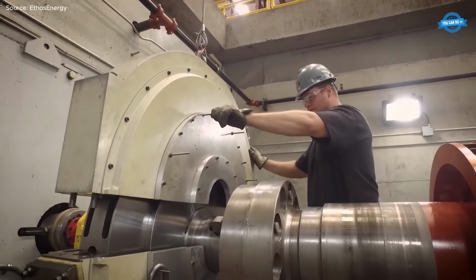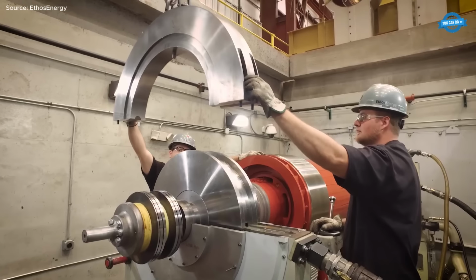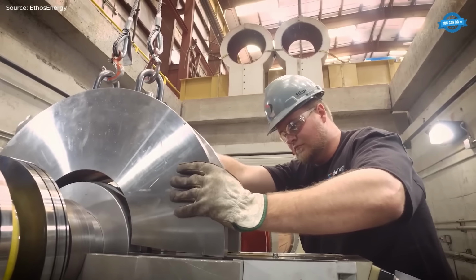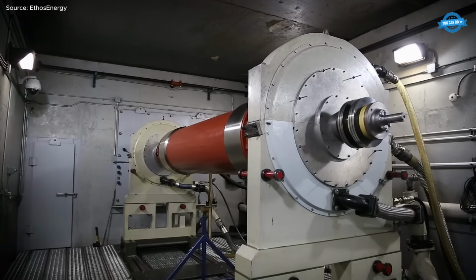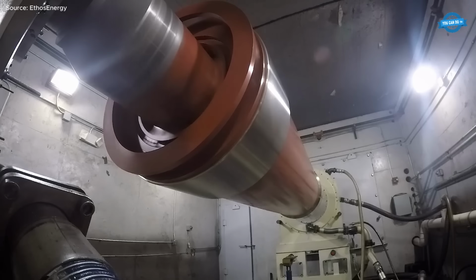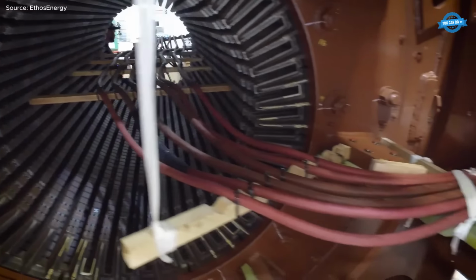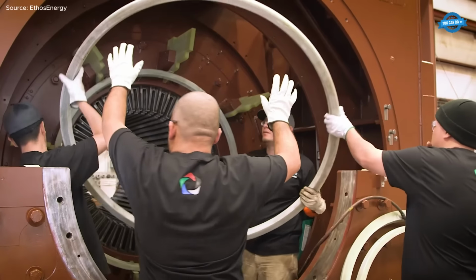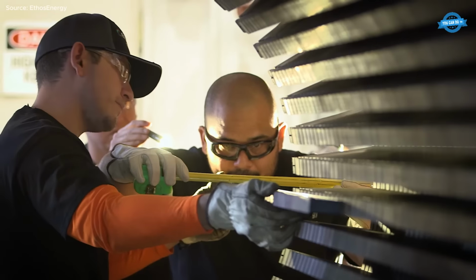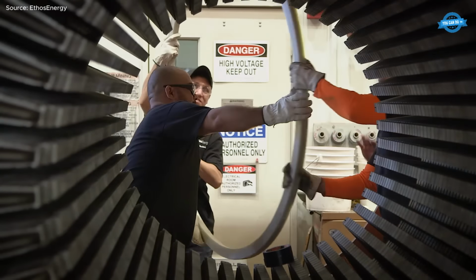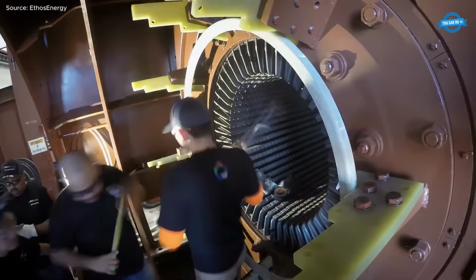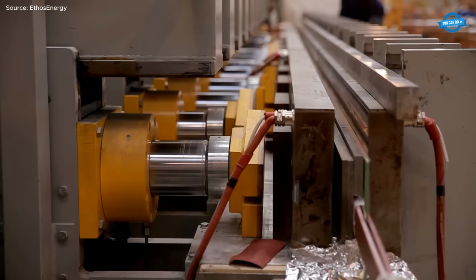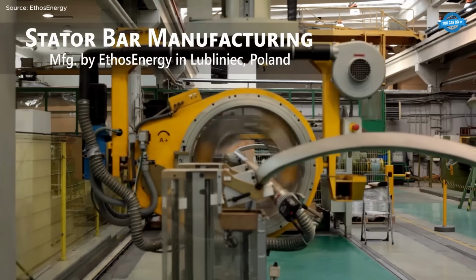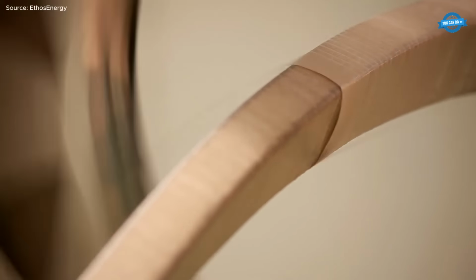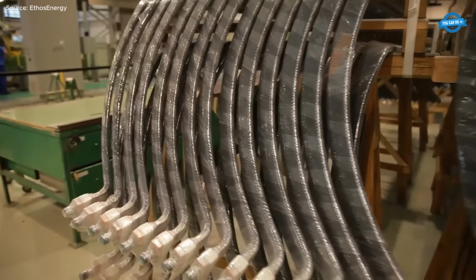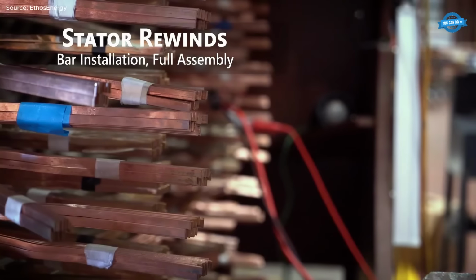On the stator side, comprehensive electrical testing evaluates insulation integrity, partial discharge levels, and core condition. Replacement stator bars, manufactured by Ethos Energy in Lubliniec, Poland, are produced to exact specifications before shipment for installation. Stator rewind projects include bar removal, slot preparation, precision bar installation, connection brazing, and full assembly. Supporting these processes, in-house machining of parts restores critical tolerances on shafts, journals, coupling fits, and structural components, returning generators to dependable, long-term service.